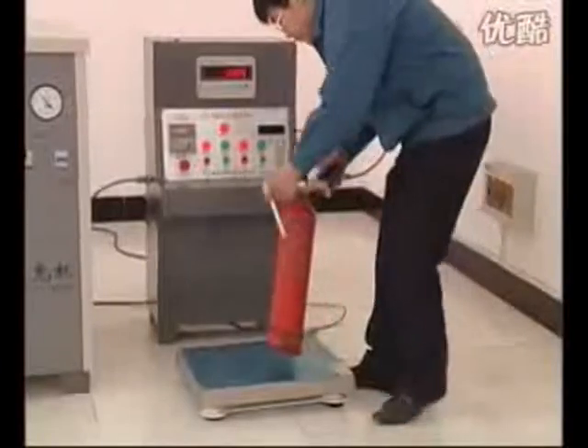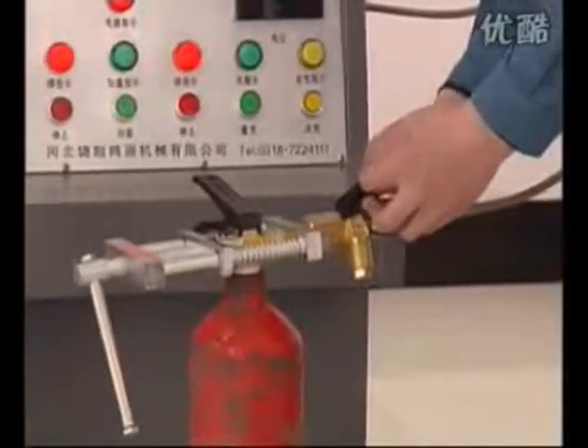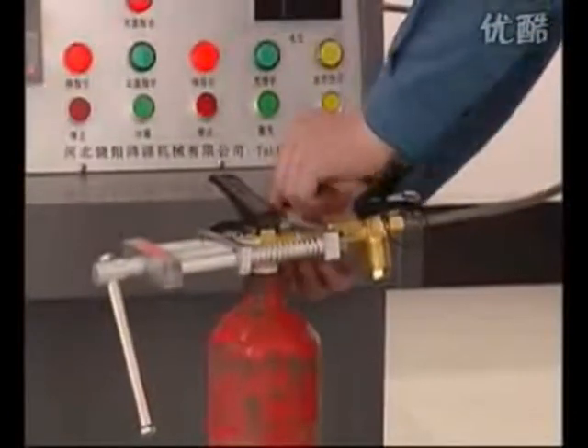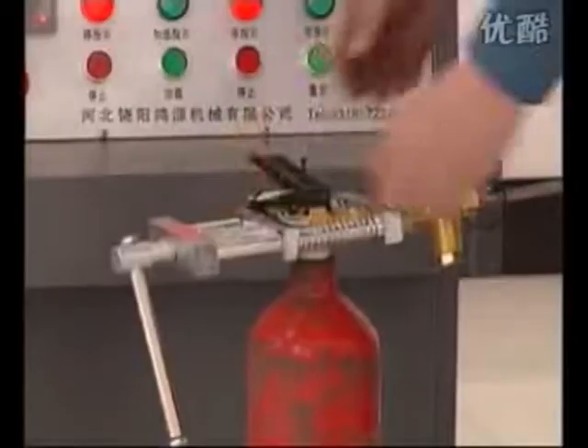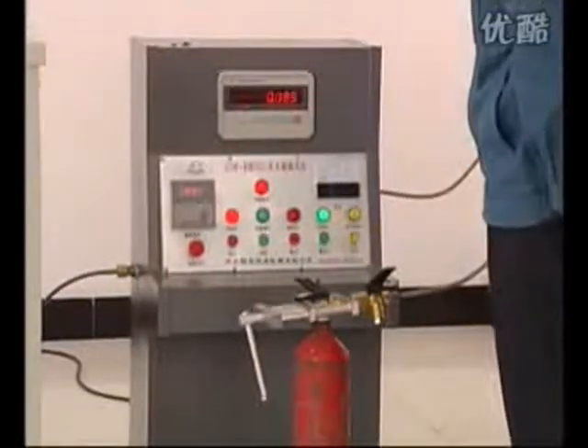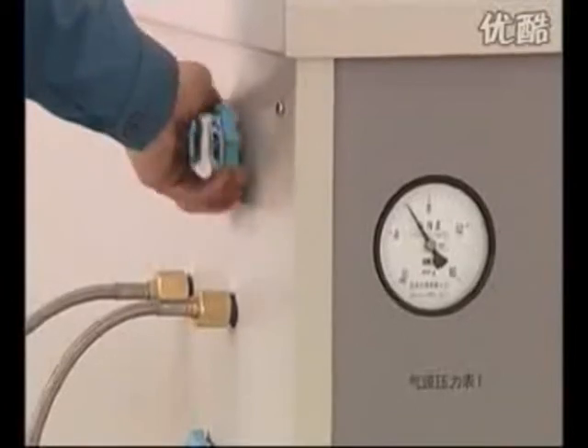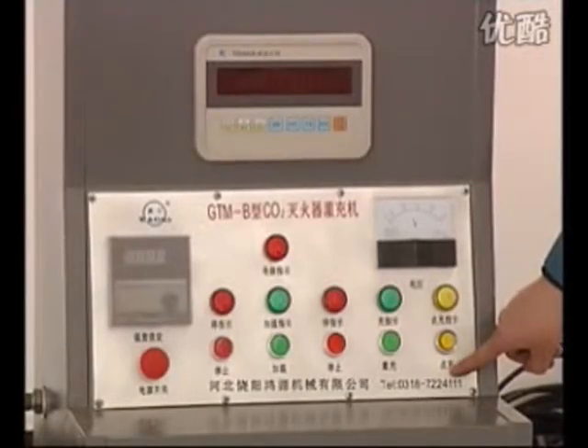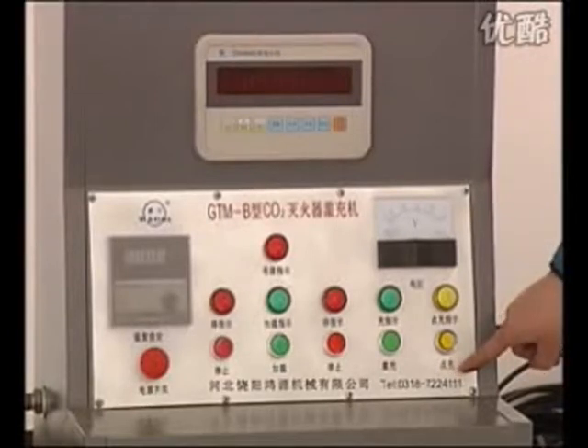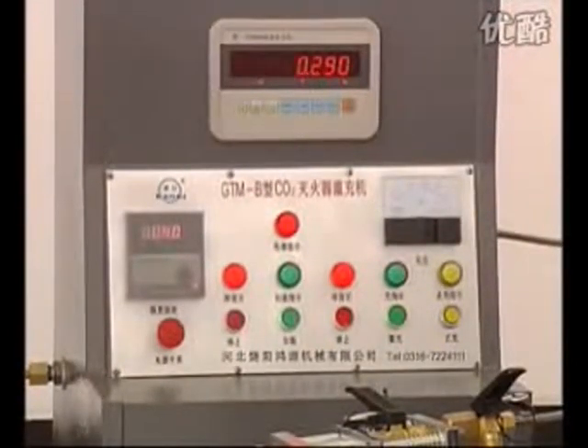Plug in the insurance pin of the safety valve and extinguisher respectively. Place the extinguisher on the electronic scale which has the fixture set. Open the filling switch to begin to fill. If the gas source pressure meter and charge pressure indicator readings are consistent, this expresses that the pressure in the cylinder source is low — open the other gas inlet valve to supply the charge pressure. If the extinguisher has not been filled fully, press the bit-by-bit filling button to supply the charge. When the electronic scale indicator shows the extinguisher has arrived at the filled weight, close the charge switch.